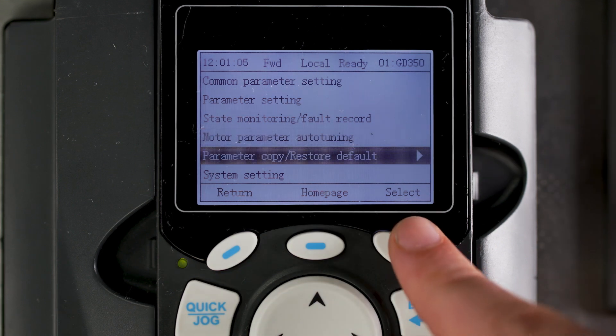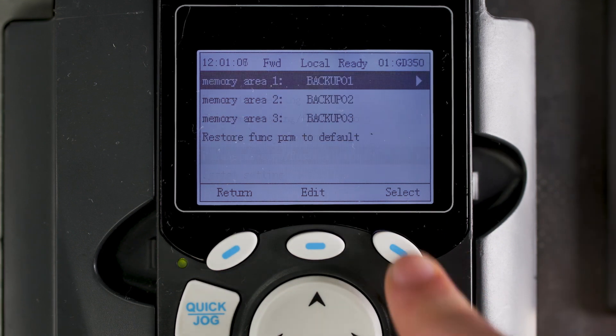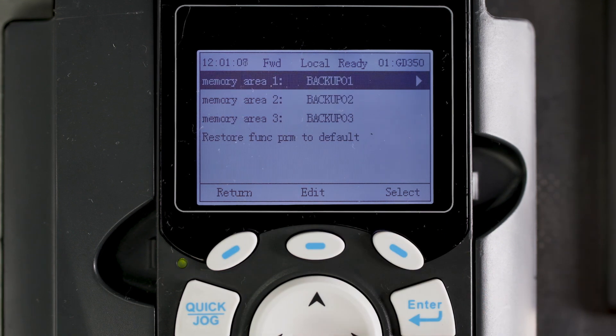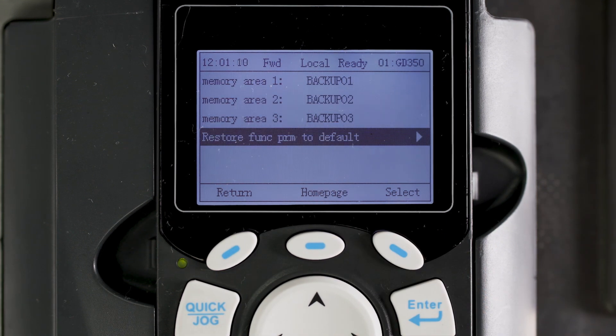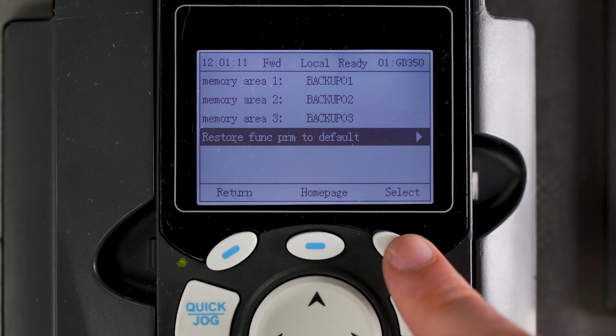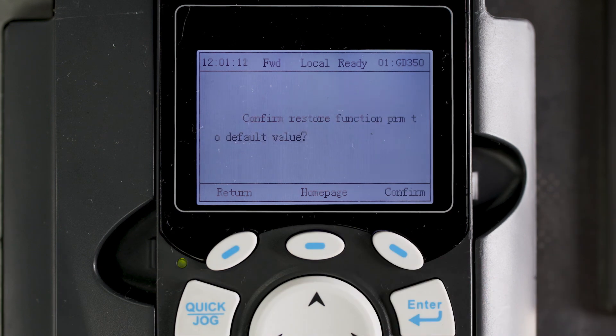The P06 parameter group is used to customize the output terminals. The P17 group parameters are the state check functions, which could help diagnose issues like an analog input discrepancy. If you need to reset the drive to factory default, use the parameter copy and restore default function on the main menu.